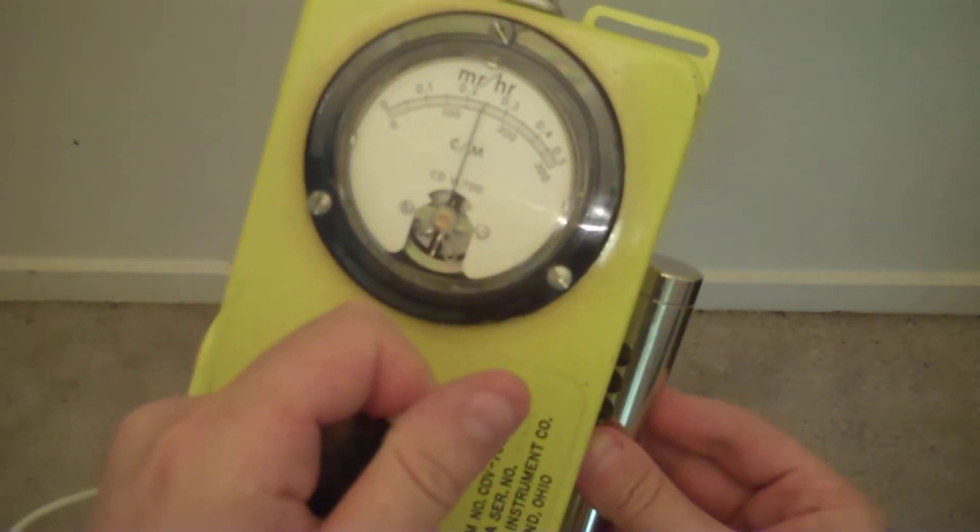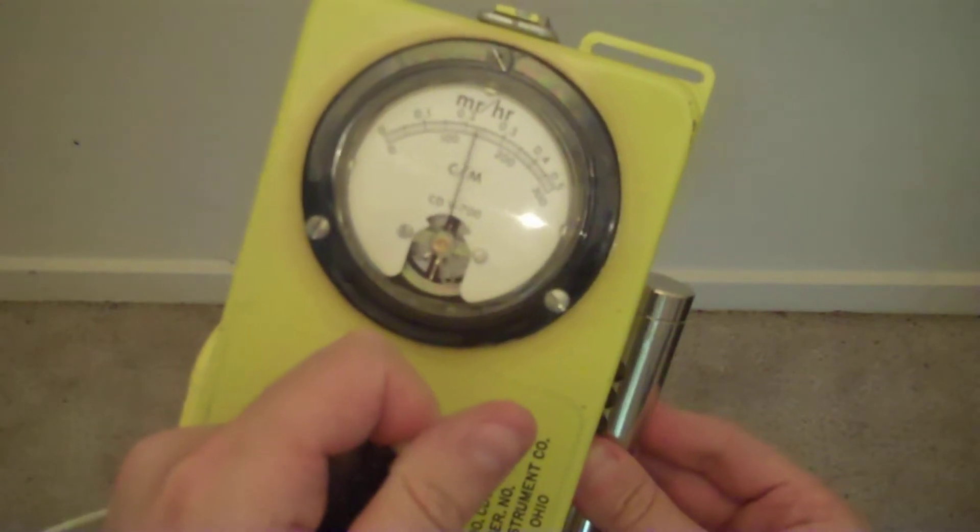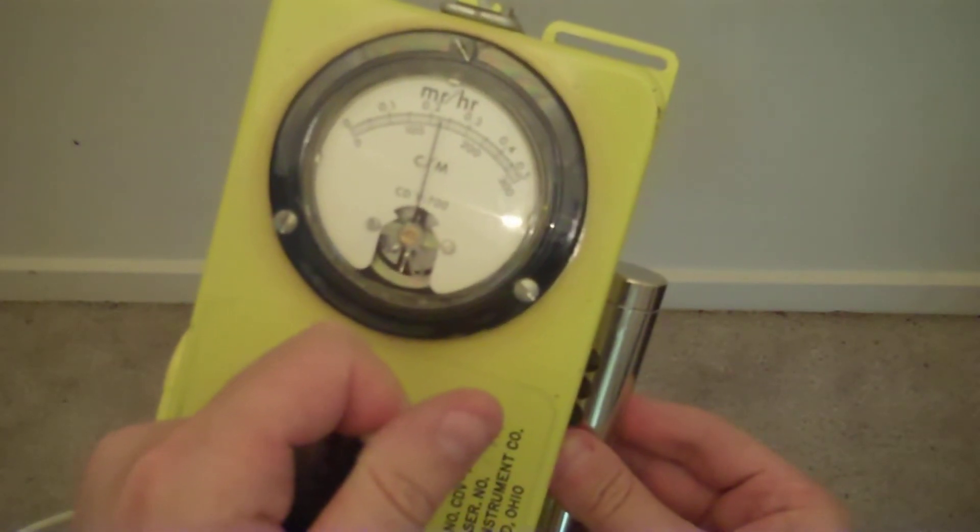As you can see, we are reading between 2 and 3 milliroentgens per hour on the times 10 scale, so we know that we are calibrated.